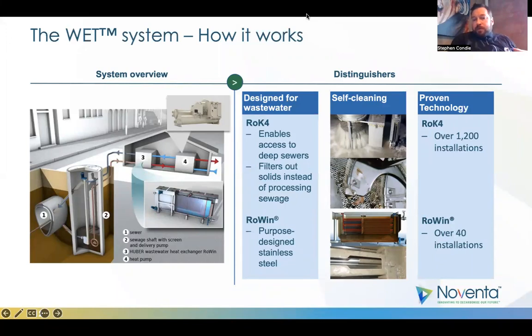With that ROK4, it's a fairly robust component. It's sold to municipalities for lift stations when they need large sewer conveyance distances. The RoWin heat exchanger, they've got over 40 installations, one of which being at the American Geophysical Union in Washington, DC, as well as a number of projects throughout Germany, Sweden, Poland, Switzerland, and soon to be again in Scotland and the UK. The benefit to the self-cleaning mechanism is that it prevents any solids buildup inside the heat exchanger.